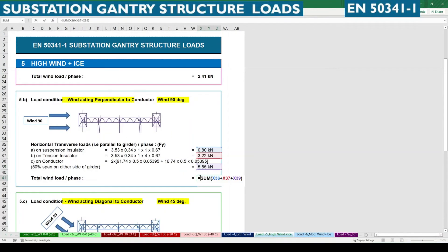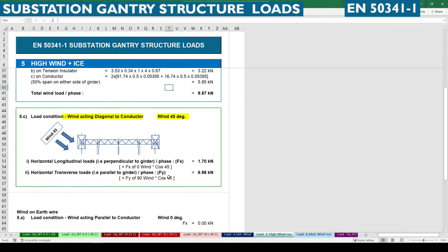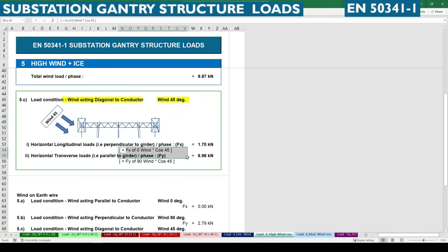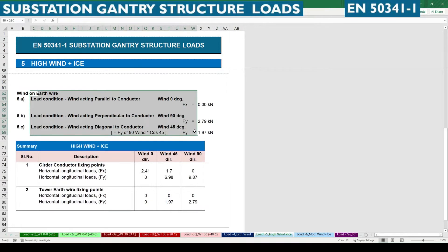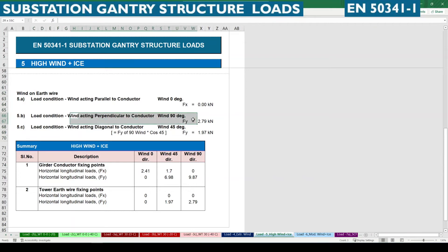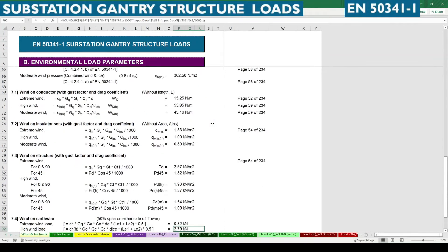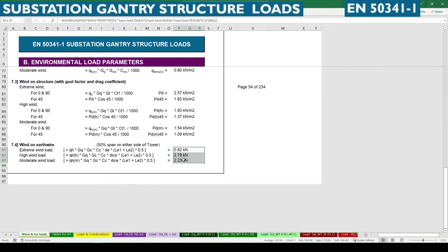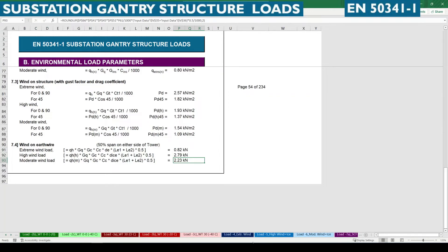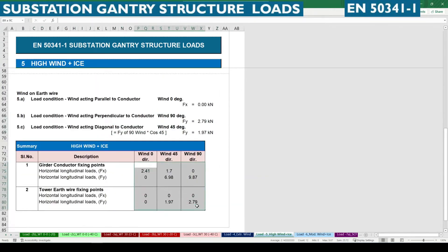This gives the summation of wind forces in the direction perpendicular to the conductor span. For diagonal wind we multiply by cos 45° in the respective directions. For earth wire, there is no wind acting parallel; only perpendicular and diagonal direction wind applies. The high wind value for earth wire calculated earlier is multiplied by cos 45° for the diagonal wind case. This is the summary for the high wind plus ice case.